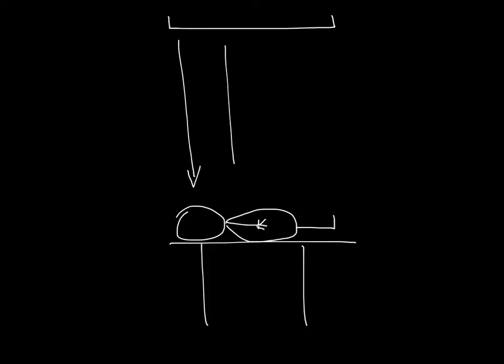So let's draw a laminar flow diffuser in the ceiling and our operating table with our poor patient on it. Now I mentioned last time that laminar flow diffusers are not truly laminar. They're actually unidirectional flow non-aspirating diffusers. Slight differences in airflow velocity, especially at the edges of the laminar flow diffuser along the ceiling, can cause some induction into the air stream.